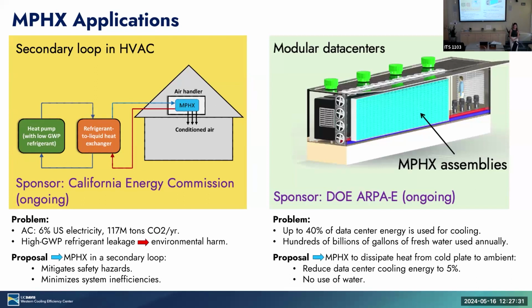The reason is that when you have phase change happening in one of the fluids, the configuration doesn't really matter because of the constant surface temperature boundary condition, so it's not as good. But if your evaporator or condenser has a significant sensible portion, then it will make a difference.